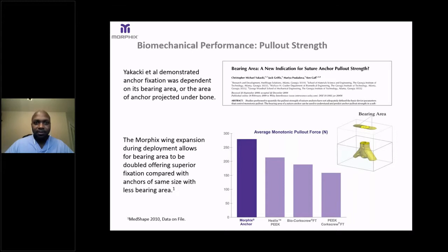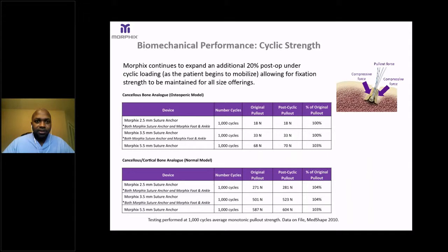Here's a paper by Yakacki and colleagues demonstrating the biomechanical performance and improved pull-out strength of the Morphix anchor. Yakacki et al. demonstrated that anchor fixation was dependent on its bearing area — the area of the anchor projected underneath the bone. The Morphix wing expansion during deployment allows the bearing area to double, offering superior fixation compared with anchors of a similar size with less bearing area. The Morphix device continues to expand an additional 20% postoperatively under cyclic loading, so as the patient begins to weight-bear and progress in rehab, the pull-out strength of the implant improves.